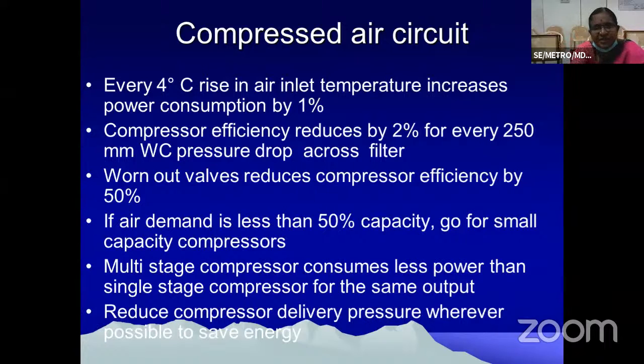Potential to save energy in the compressed air circuit. Every 4°C rise in air inlet temperature increases power consumption by 1%. Compression efficiency reduces by 2% for every 250 mm WC pressure drop across the filter. Worn out valves reduce compressor efficiency by 50%, so replace them whenever needed. If air demand is less than 50% capacity, go for small capacity compressors. Multi-stage compressors consume less power than single stage compressors for the same output.